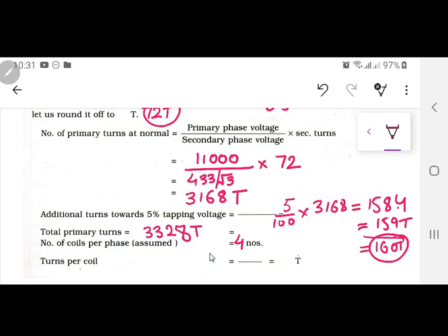Yes, it could be, but 3 cannot work, I said. The problem is that with 3 you have a center one and then the 2 other ones. Here for the withstand capabilities, we want the center coils to have a little larger distance so that they can have more withstand capability. So avoid 3. Okay? You can have 4, you can have 5, you can have 6. In fact, when we go to the power transformer, when the power transformer will be discussed, you will see that these number of coils will increase to even 15. So this is totally again dependent upon the design.